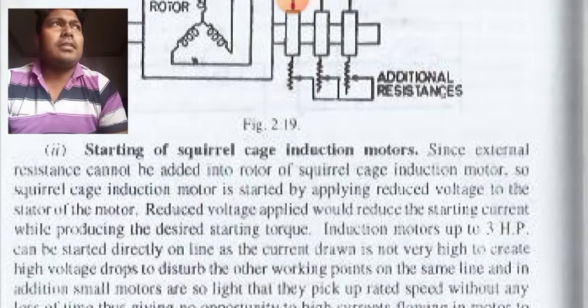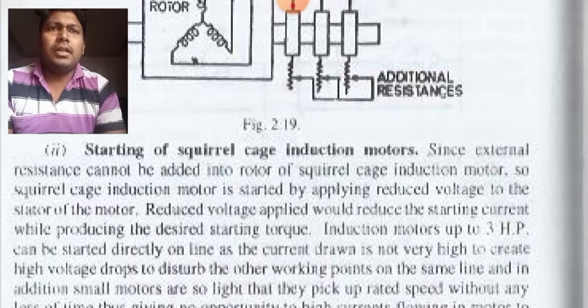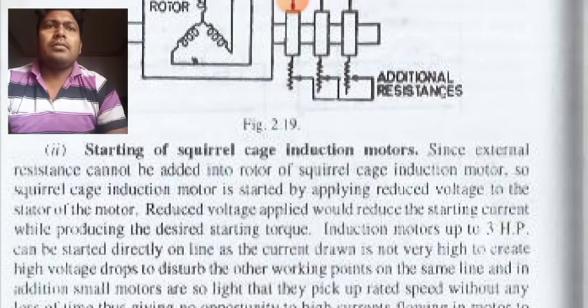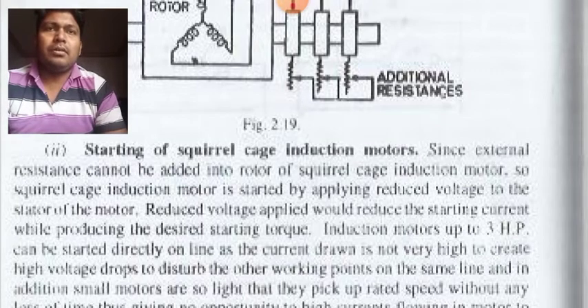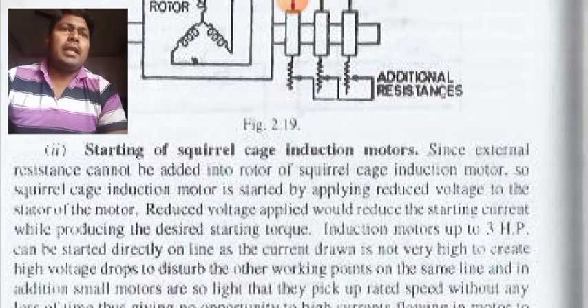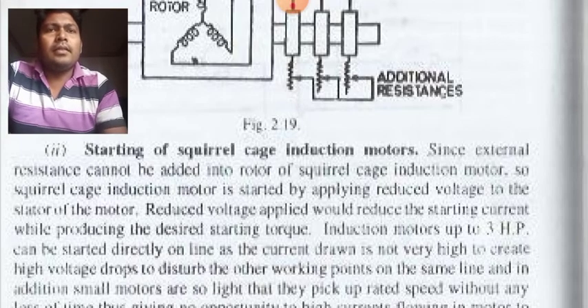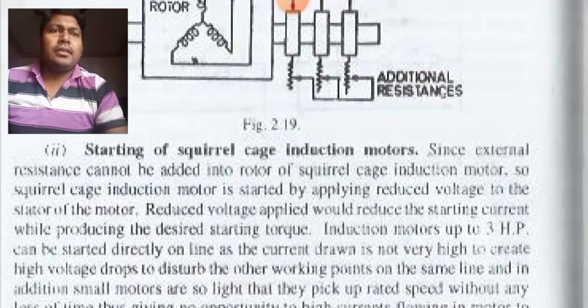So how to start then? Our intention is to limit the current, and if we cannot limit the current, then it will draw a heavy amount of current, resulting in damage of the motor. So there has to be a reduced amount of current taken by the motor. So we usually employ a reduced voltage technique. Usually this function is performed by the use of an auto transformer. So we have to apply a reduced voltage to the stator of the motor. Reduced voltage applied would reduce the starting current while producing the desired starting torque.